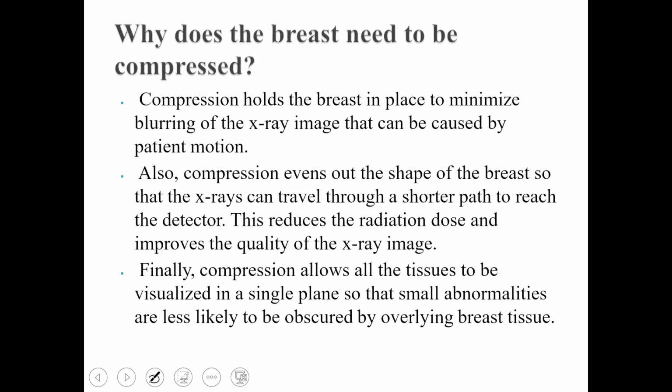If the patient moves here and there, the breast will not be held in the same position. So the X-ray will be deflected here and there, and you will not get an accurate image of your breast. That's why we need the compression plate, so the breast is held in one position. If the patient moves, the breast will remain in the same position. It will not move here and there with the movement of the patient.